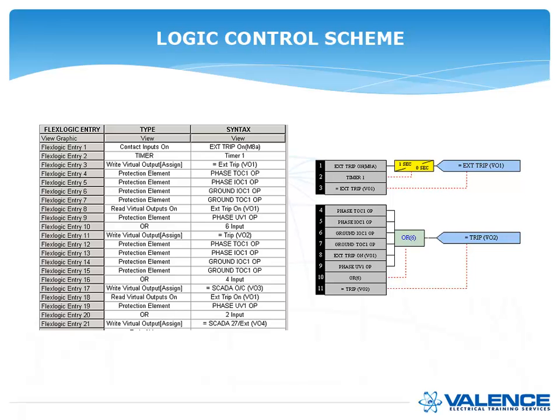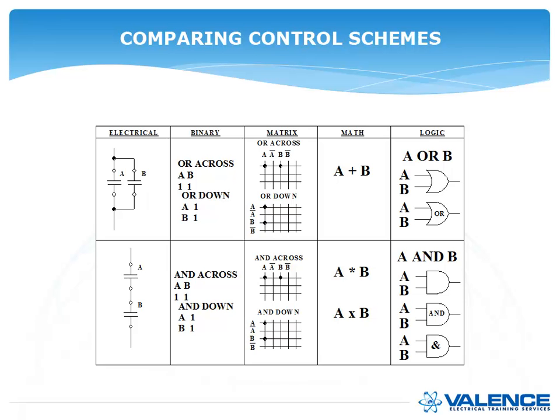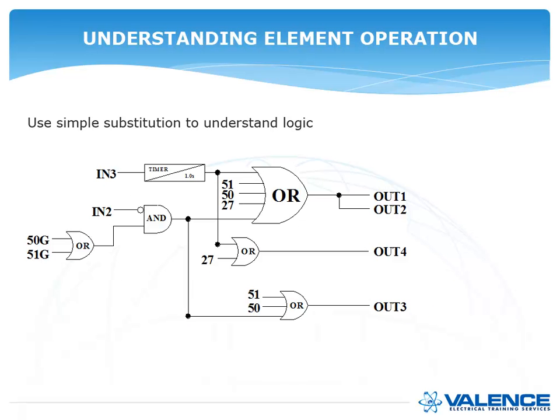So here is a chart that combines all of the different schemes. So if I have an electrical schematic with two contacts in parallel, in binary, that would mean, if it was OR across, that would mean two 1s together. Or if OR was down, that would mean an AB with a 1 and 1 like that. And then you can have it also shown as a matrix. In math, that would be A or B. And then you can have a logic scheme. So you can see you can translate from one scheme to another, or you can just translate everything to electrical to help you understand what relays are supposed to do.